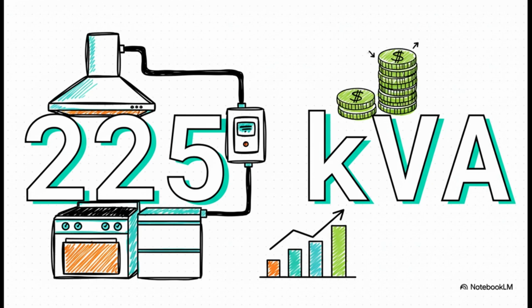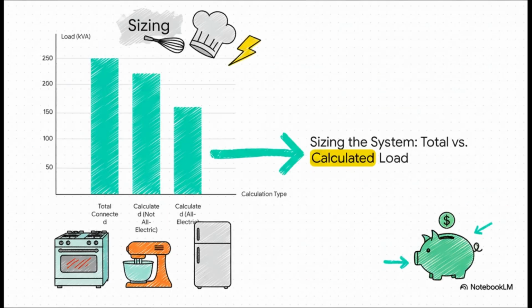For a not all electric place over 800 kVA, the multiplier absolutely tanks. It drops to just 20% of the amount over 800 kVA. 20%. Seriously. Plus a base of 476.3 kVA. So once a mixed fuel restaurant gets truly massive, the code assumes the additional electrical load above that 800 kVA mark is incredibly diverse. Like, it's mostly lighting, maybe huge banks for refrigeration, IT systems, convenience outlets. Stuff that's very unlikely to all peak at once compared to the core kitchen load, which is partly gas anyway. Exactly. So only 20% of that extra load needs to be factored into the service size.